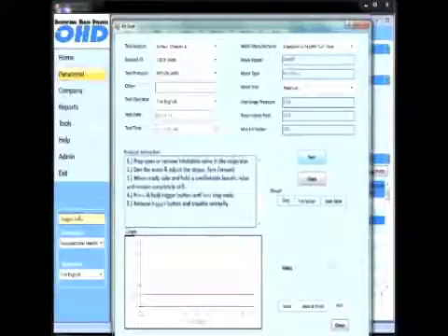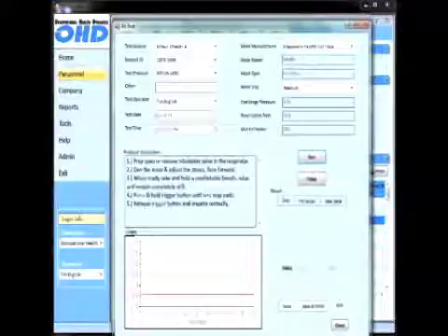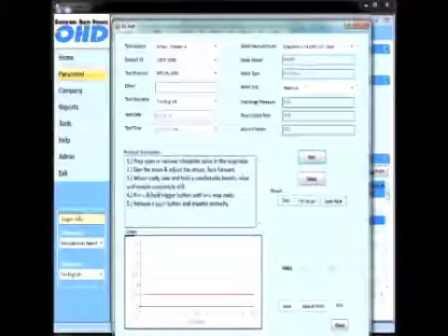The QuantiFit will perform a series of beeps, and then the software will be ready for testing. In the left screen, you'll see the protocol instructions for each step of the test, and at the bottom, you'll see a graph that shows the progress of the test. Instruct the test subject to take and hold a comfortable breath, and then press and hold the trigger button for the 8 seconds of the test.